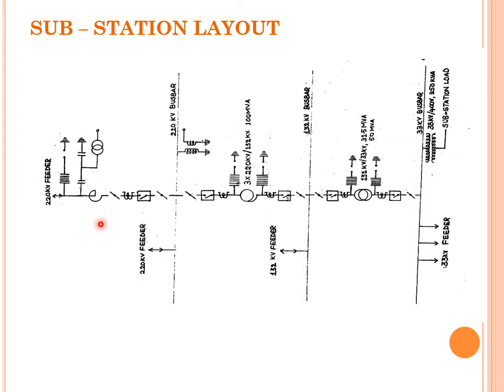The 33 kV level is the nearest substation to our houses. You can see these are the feeders or buses. On both sides of the incoming feeder or buses you can see isolators and circuit breakers. Isolators are no-load switches whereas circuit breakers are on-load switches. Whenever any fault comes, the circuit breaker trips first, after which you can operate your isolators.